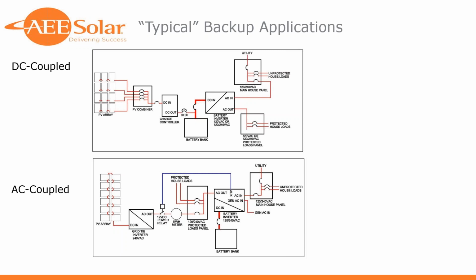The biggest drawback to turning the PV inverter off is that once you introduce AC power again, it's going to qualify that grid, and you've got a 5-minute count up, which, depending upon how you size the system and how much battery you've got, is really going to determine whether you make it to that 5 minutes or not. I've seen systems designed where the loads were not large enough to keep the PV inverter running during outages. The PV inverter shuts off, the battery inverter depletes the battery and tries to animate the PV inverter again, but in waiting for the 5-minute count up, the battery gets to low battery cutoff.